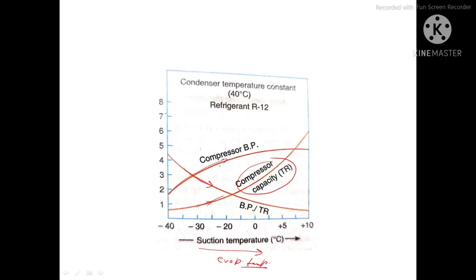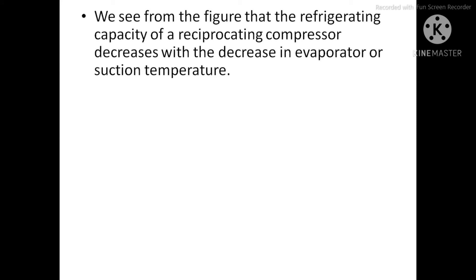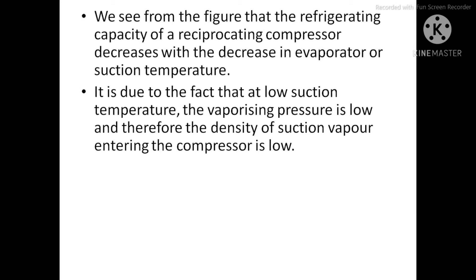From the graph, as the suction temperature increases the compressor capacity also increases, or conversely, as suction temperature decreases the compressor capacity decreases. This diagram is for refrigerant R12. We see from the figure that refrigerating capacity of a reciprocating compressor decreases with a decrease in evaporator or suction temperature.